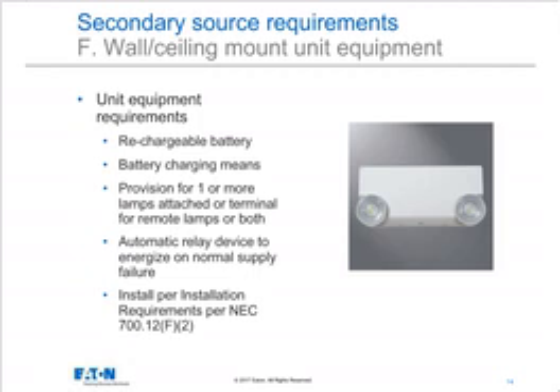So these all have to be wired to 120 volts AC typically. So that's extra wiring in the building, which is dedicated to emergency lights only. So that needs to be considered if you're comparing the cost of a UPS centralized system or a wall-mounted secondary source equipment like we're talking about here.